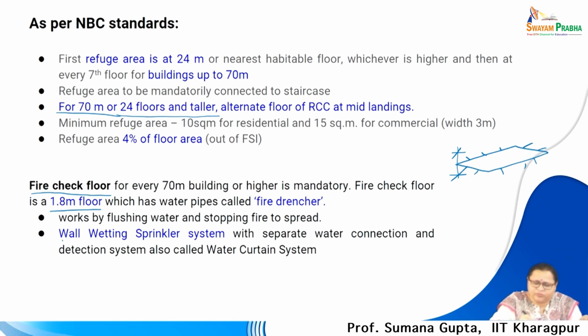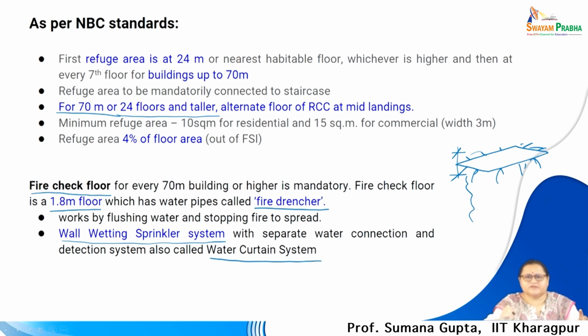So, what is it doing? It is a wall wetting sprinkler system. If the fire is trying to move up, these start pouring water on all sides of the building facade. So, the building is washed with water, and that is called a fire drencher. We are washing the building facade with water. It is also called a wall wetting sprinkler system with separate water connection and detection system, also called a water curtain system. Technically it is a fire drencher, also called a wall wetting sprinkler or a water curtain system. We had seen sometimes the glass windows can have a wetting sprinkler system, so that the fire does not damage the glass.